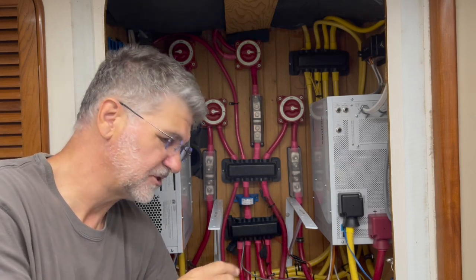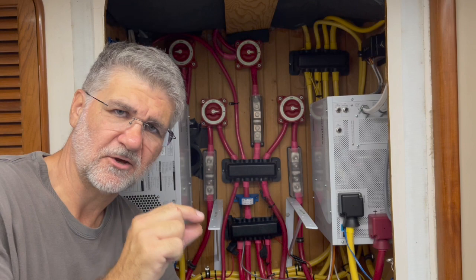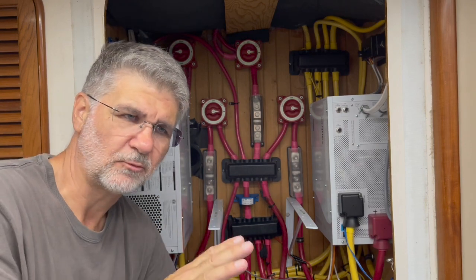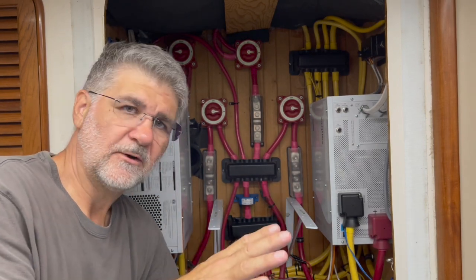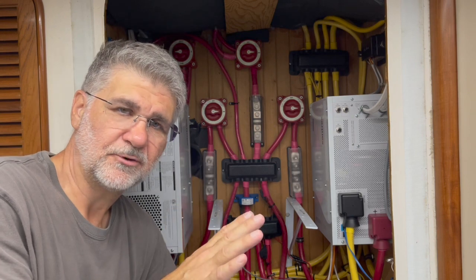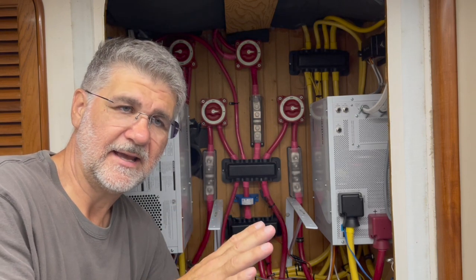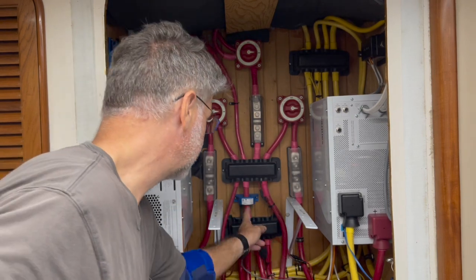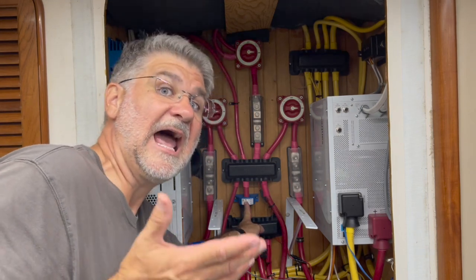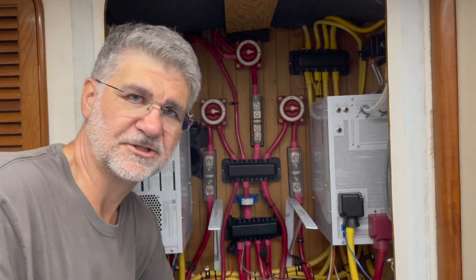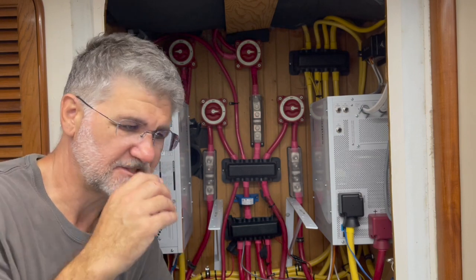I contacted them recently because I had readings that were way off. If you remember, when I originally tested it, it seemed pretty close, but I wanted to make sure everything was right. Once I was out at anchor putting some serious amperage into the battery bank, I saw it was measuring about half of what was actually being put in. Obviously that's a serious issue.